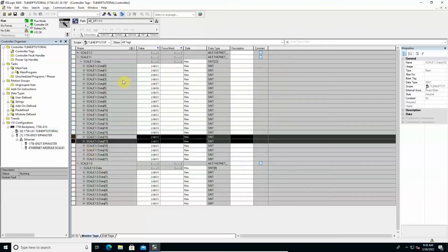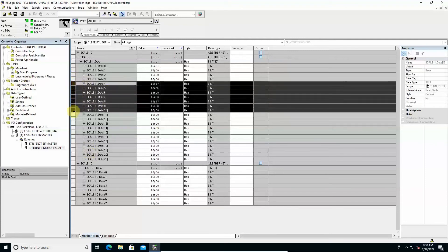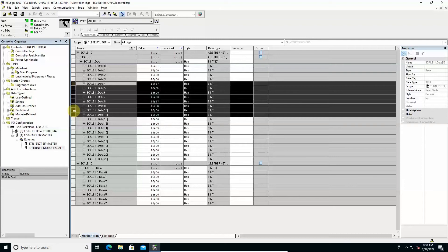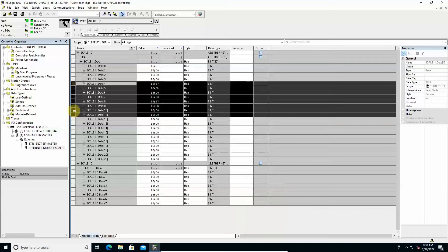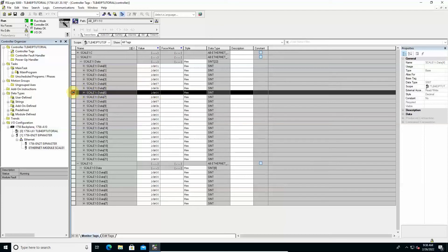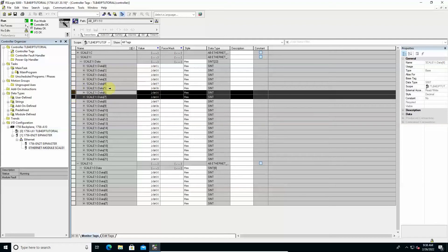With reference to the current values some observations regarding the weight values management. The 2 values are currently identical because no tare is applied. For both of them the absolute value is transmitted including the decimals but without the decimal point. Each value is made up of 4 bytes. In the case of the Ethernet IP the order in which the bytes are published by default is the little endian. Therefore the bytes of lower value are the first. At this moment for example for the gross weight, the lower value bytes are 87 and 0b while the higher value bytes are 00 and 00.